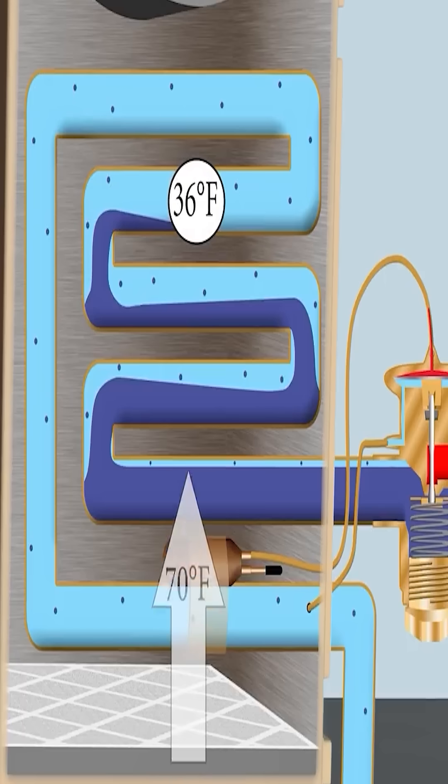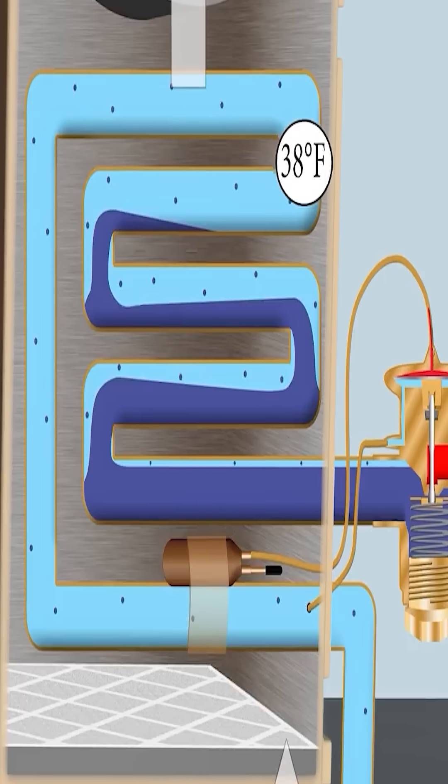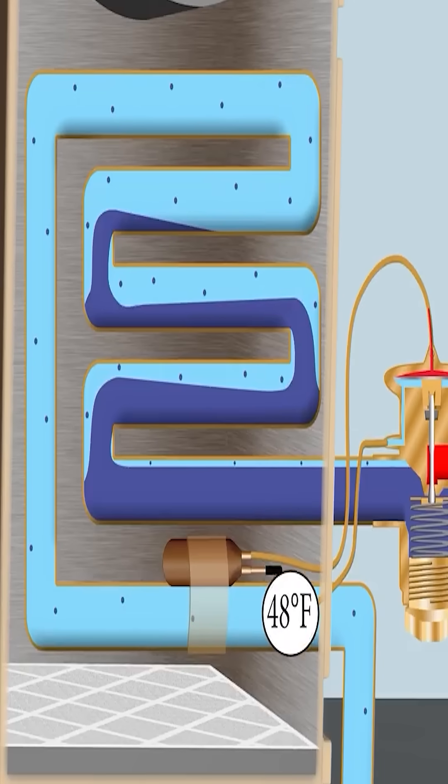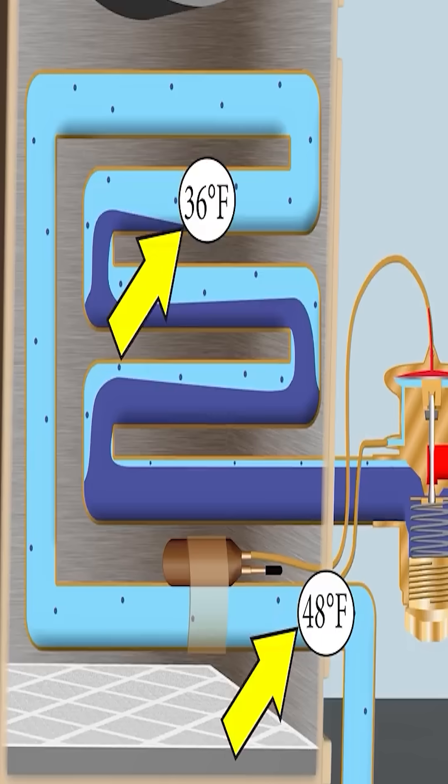But anyway, you have 36 degrees here and it's going to increase in temperature as the vapor travels through the refrigerant tube until it comes out of the coil right over here at 48 degrees. So 48 degrees minus 36 degrees, that's 12 degrees of superheat and superheat is the temperature increase of the vapor refrigerant.